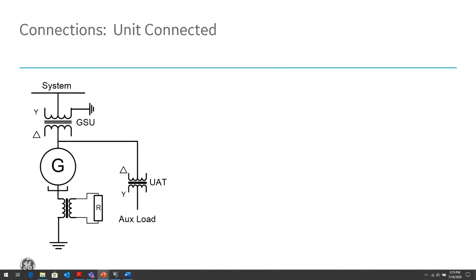What we're going to talk about today is going to be focused on this connection, which is the unit connection. You'll find this mostly on large utility or industrial systems, with a transformer between the generator and the system, and the generator is high impedance grounded. Typically, you might have an auxiliary transformer, usually there to provide some light and power load, some auxiliary load when the generator is running, or when the generator is offline, where it can be backfed from the system. Both the GSU and the auxiliary transformer are delta connected on the generator bus connection, again to isolate the grounding from the system and from our loads affecting the grounding in the generator. So if there's a fault out in the system, or out in the load section, the generator does not see that ground fault, only faults within its zone.